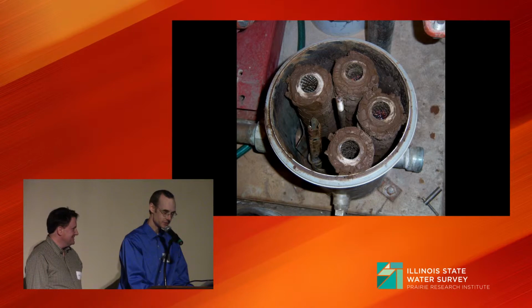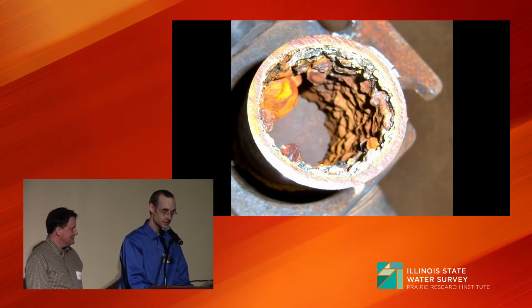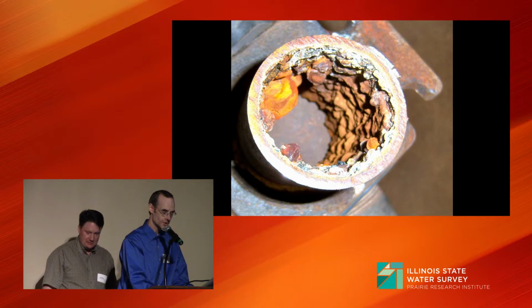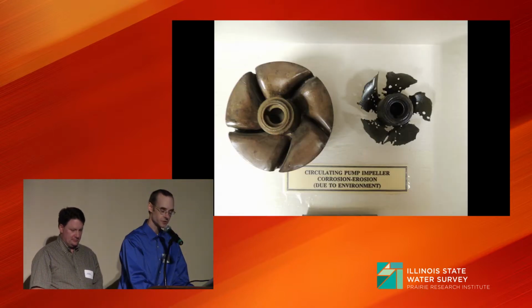Corrosion rate has a drastic influence on service life. The ideal corrosion rate of 5/10,000ths of an inch per year gives a service life of 250 years. At 1/100th of an inch per year, that life is 10 years. Other mechanical parts of the system can also be destroyed by corrosion, as shown in this picture of a severely corroded pump impeller. So one might say, we are the only 3 guys in the state who actually get paid to make stuff not happen.